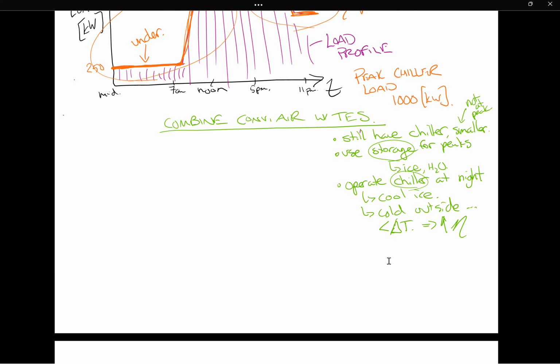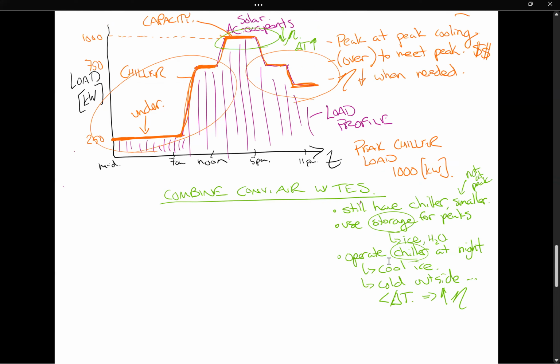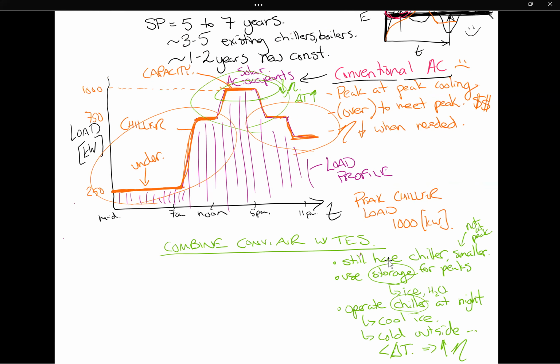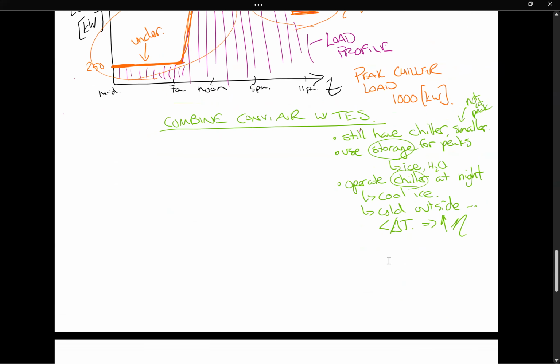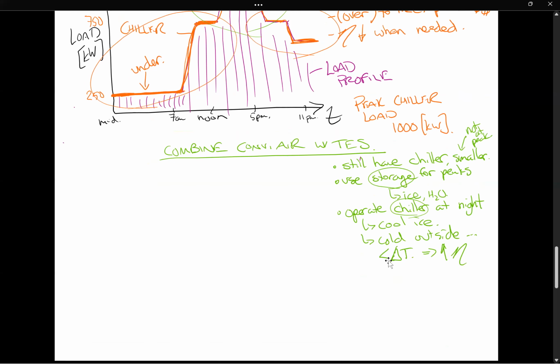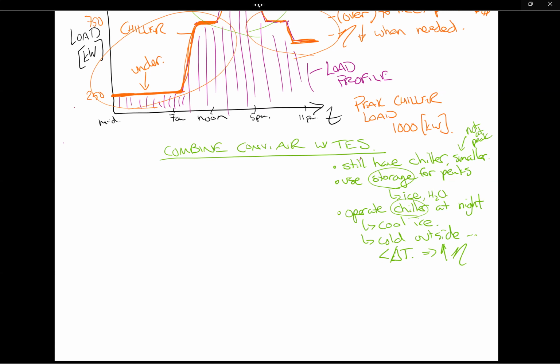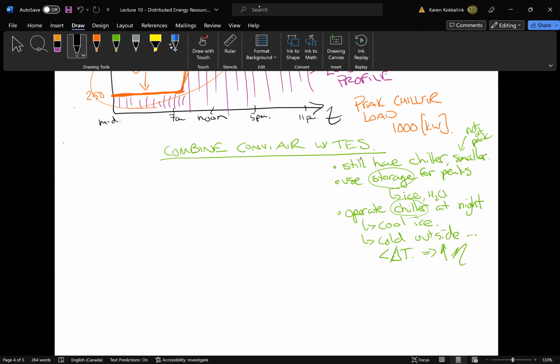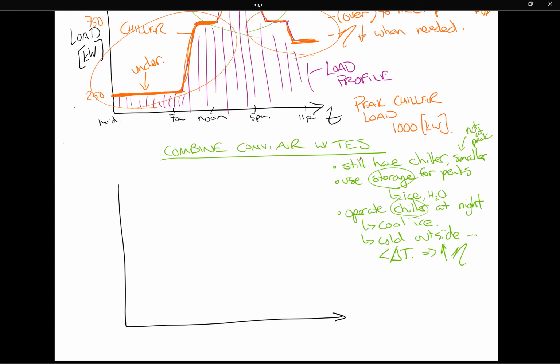So let's operate this chiller at nighttime. Let's not put the cooling into our facility where our occupants are — let's put it into some ice, and take out that ice at this peak time. Let's see what that looks like. Let's look at this building load again, do the same thing — here's our time, and here's our load.